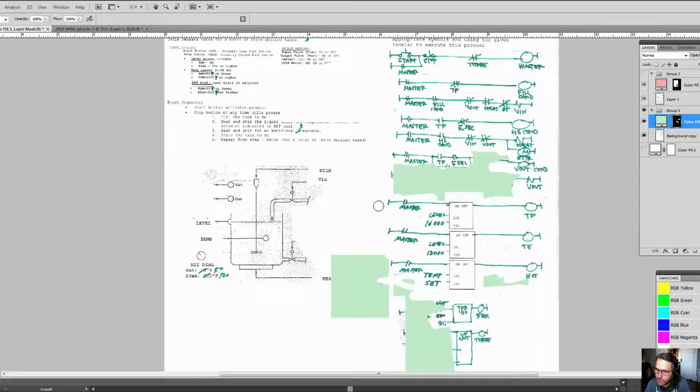And so this is going to drain until you get an empty signal. So here's what I was talking about before. How are you going to cut this V out when the tank goes empty? You have to keep in mind that TE, that's going to go high when you have an empty signal. So you want this active TE to cut this, definitely a normally closed. And you must latch anything that's going to drop out as soon as V out starts happening. So that would be both the high level signal and also the timer will cut out.